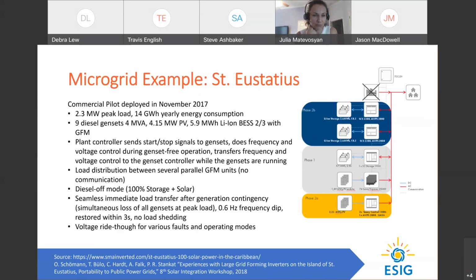Currently there is a common plant controller that sends start-stop signals to gensets, does frequency and voltage control during genset-free operation, and then transfers frequency and voltage control to genset controllers when gensets are running. It can do load distribution between 2 parallel grid forming inverters without any external communication. They've tested diesel off mode, initially just in a test environment, but now they regularly operate during daytime with diesel being off and the grid being powered just by solar and backed up by storage.